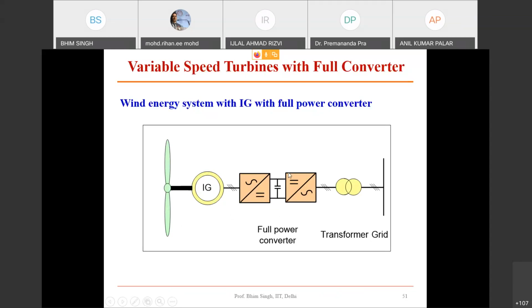The DC link voltage is controlled by the second converter interfaced to the grid, because that converter can only know how much power is coming via the DC link. So you keep the DC link voltage controlled such that as much power as comes in, that much power is transferred to the grid. This system uses full rating converters to operate at variable speed, but the speed range can be quite large.